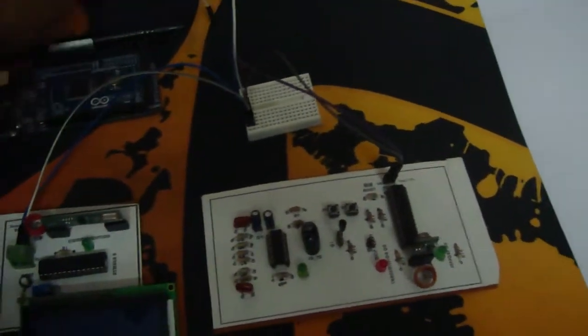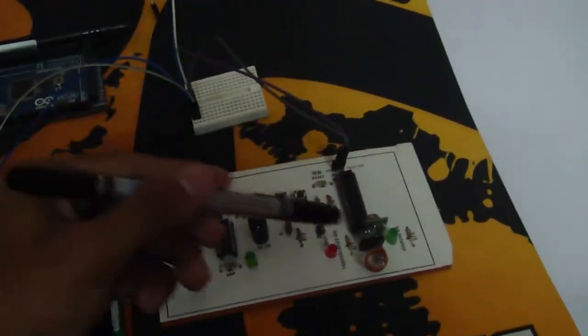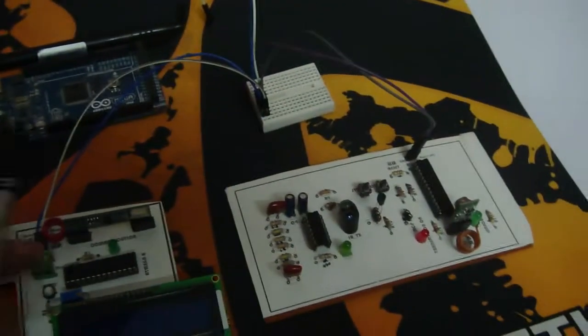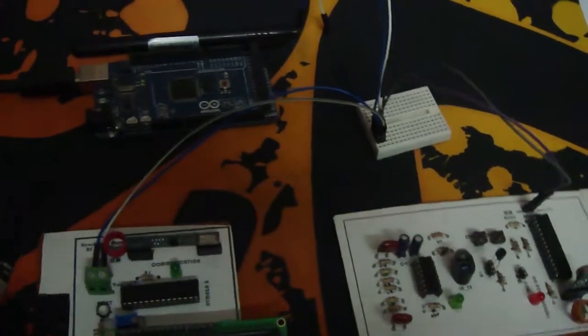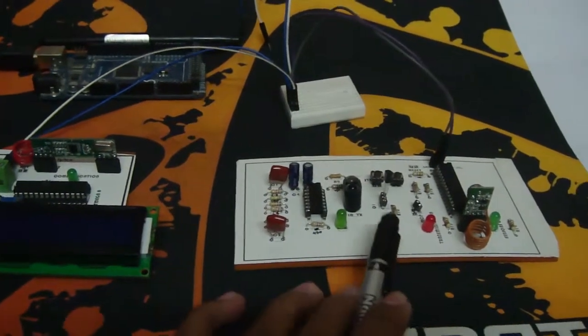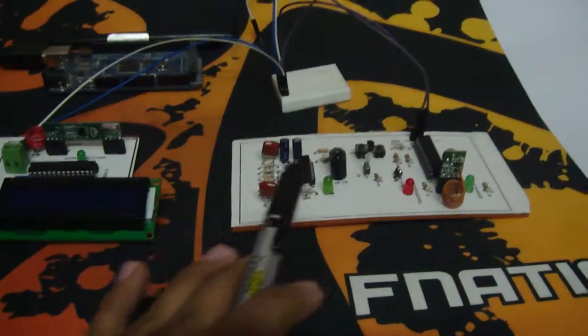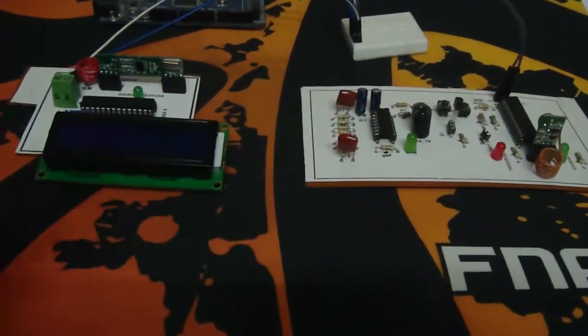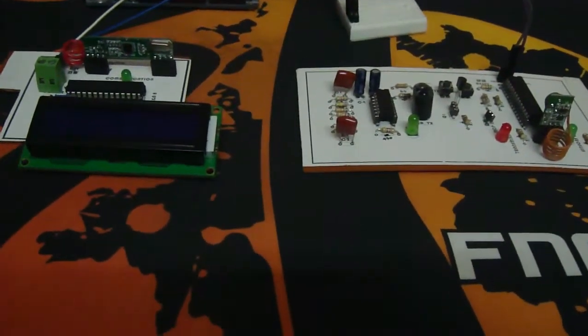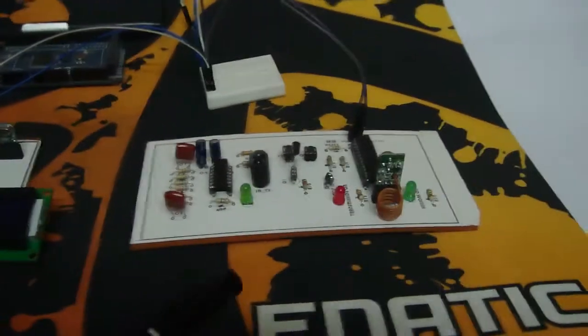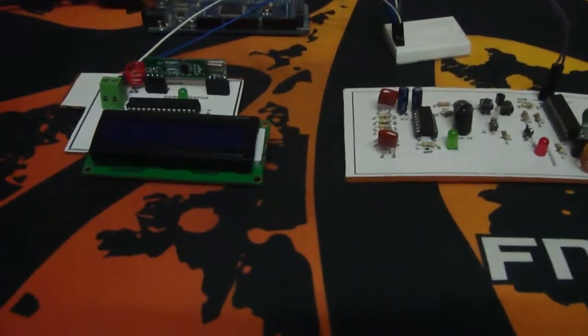But we added a new feature: the RF transmitter and receiver. This makes it more portable and flexible to use. You can keep the transmitter or heartbeat measurement system at the patient site and still read the data from a distance, depending on the RF module range.